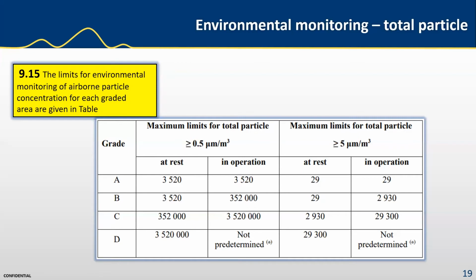For grade D, in operation limits are not predetermined. The manufacturer should establish in operation limits based on a risk assessment and on routine data where applicable. Under the notes, which I don't have shown here, note 1: the particle limits given in the table for the at-rest state should be achieved after a short cleanup period defined during qualification, with a guidance value of less than 20 minutes in an unmanned state after the completion of operations. What they're saying here is to make sure that the aseptic area is ready to do the aseptic processing, and that you've met the criteria in the table here before you actually jump into the actual processing.